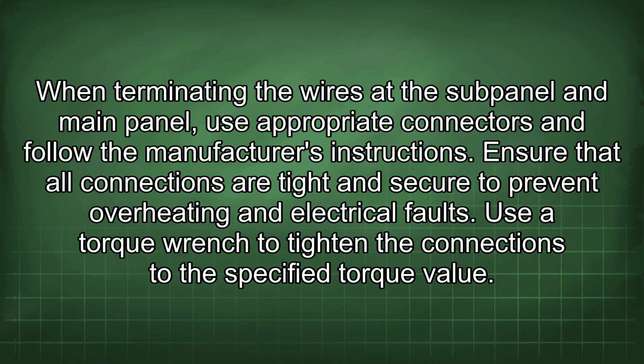When terminating the wires at the subpanel and main panel, use appropriate connectors and follow the manufacturer's instructions. Ensure that all connections are tight and secure to prevent overheating and electrical faults. Use a torque wrench to tighten the connections to the specified torque value.